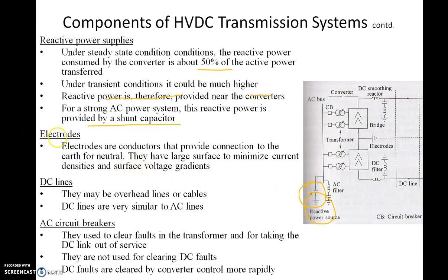Electrodes are conductors that provide a connection to earth for the neutral. The two transformers on each side have their neutrals earthed through electrodes, which have a large surface area to minimize current density and surface voltage gradient. DC lines can be overhead lines or underground cables, and they are very similar to AC lines.